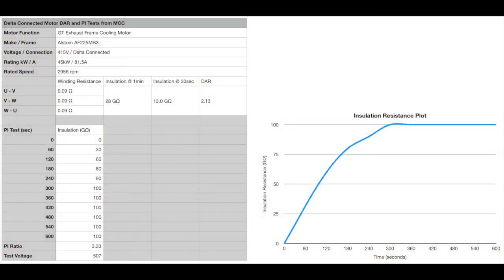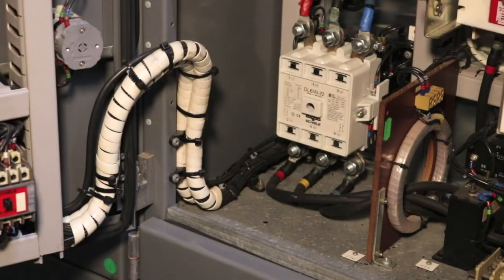For the sake of the plot I'll actually record it as 100 gig ohms. But then that test has finished we can pack up and make the panel safe ready for a return to service.